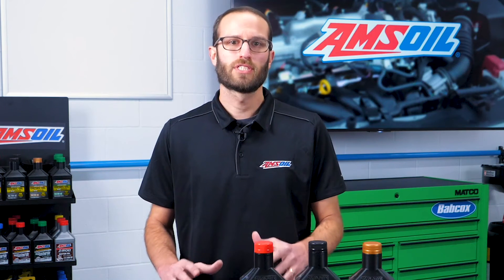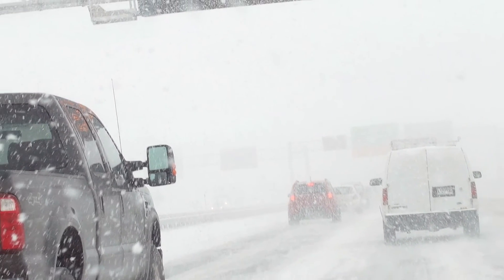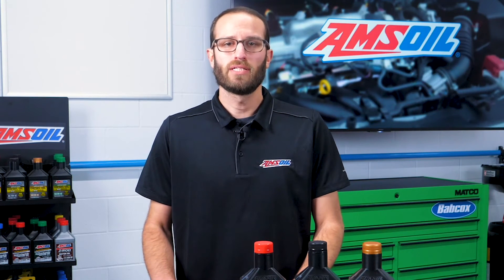Additionally, even small temperature swings can freeze your fuel — it just depends on how cold it gets. Within a 20 degree swing from 30 to 10 degrees, you might not see any freezing. However, from minus 20 to minus 40, it could be a bigger deal. So you need to be preventative in your fuel maintenance by running fuel additives that can help you protect from cold weather conditions.